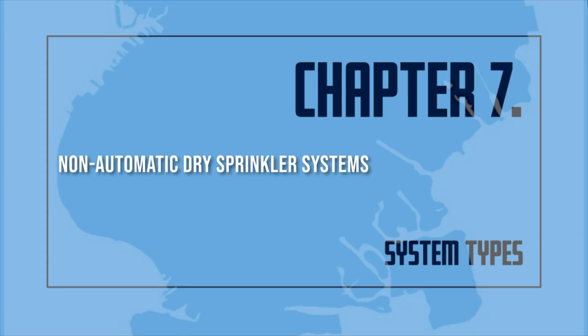Non-automatic dry sprinkler systems. In this type of system, all pipes are normally dry. Water is supplied when needed by pumping water into the system through the fire department connection. Some of these systems are supplied by manual operation of a water control valve and may be equipped with sprinklers with or without fusible links. There are several non-automatic systems.